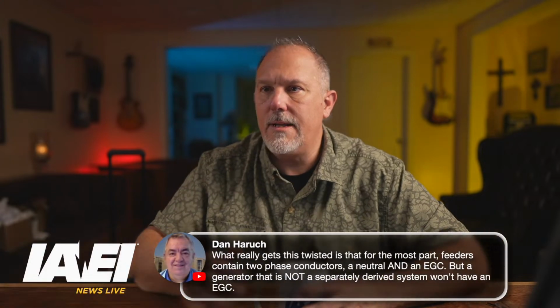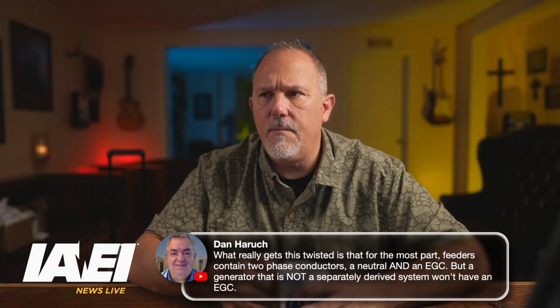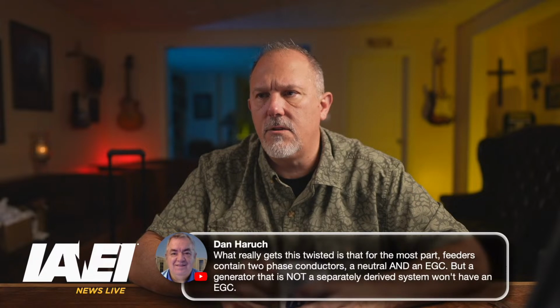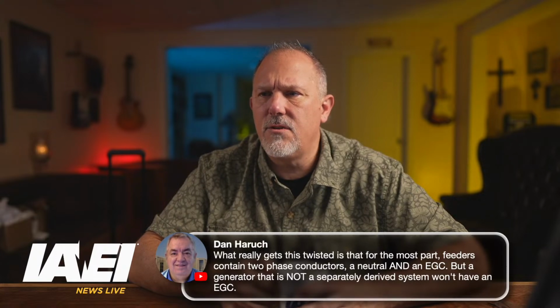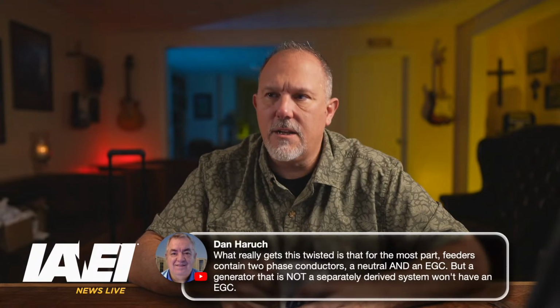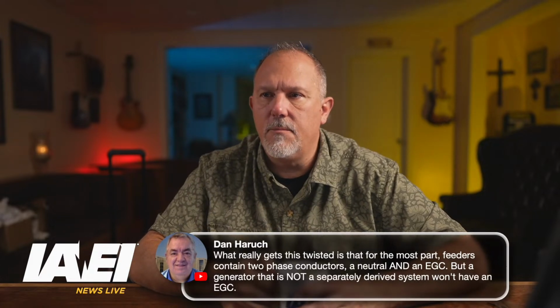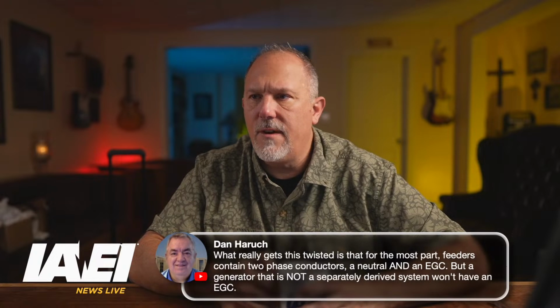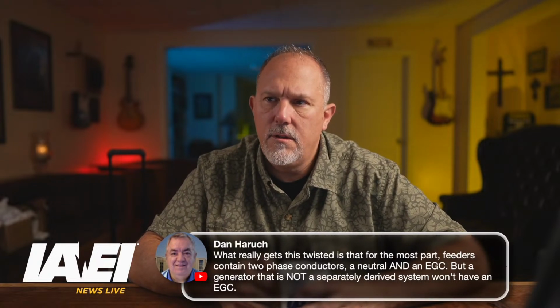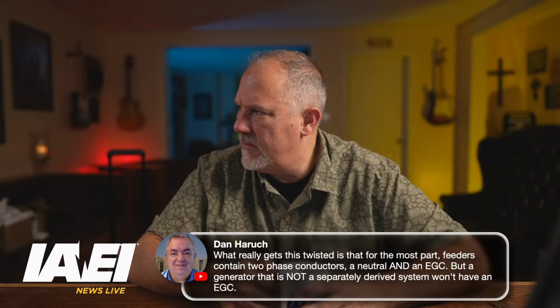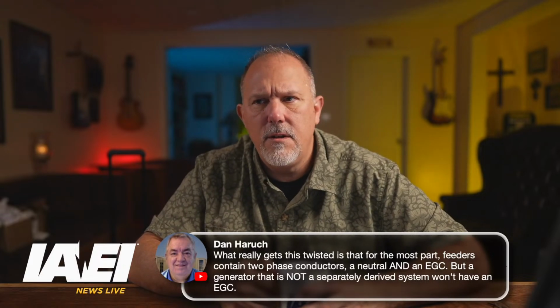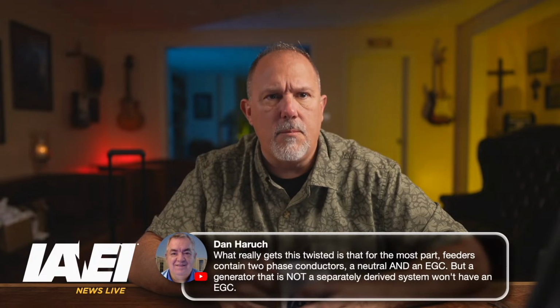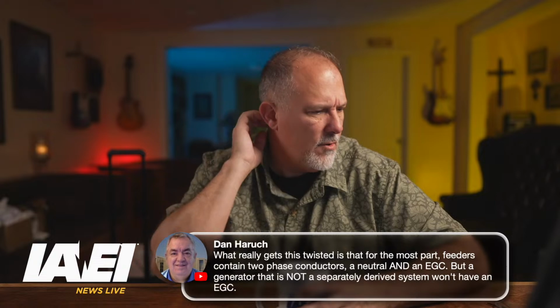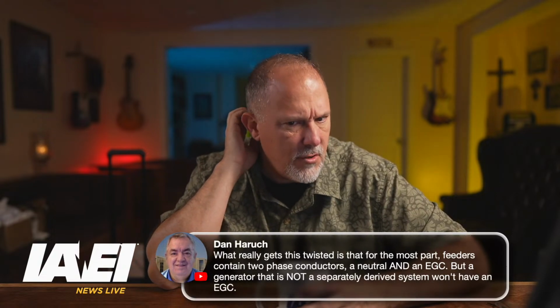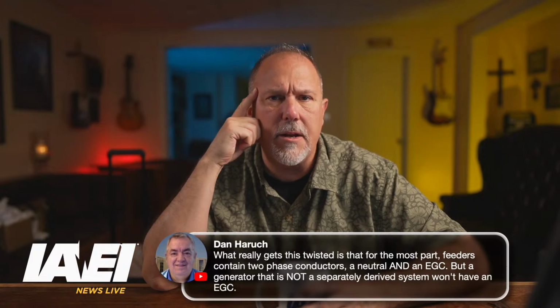Dan says, what really gets this twisted is that for the most part, feeders contain two-phase conductors, a neutral and an equipment grounding conductor. But a generator that is not a separately derived system won't have an equipment grounding conductor. You always have an equipment grounding conductor, Dan. In my opinion, you're going to have to bond everything together. So you still have to bond everything back out to that generator.